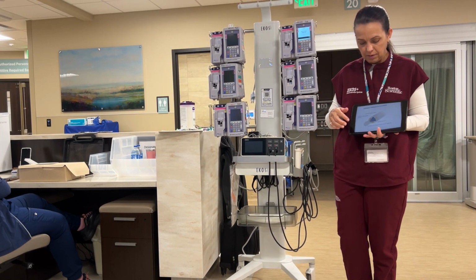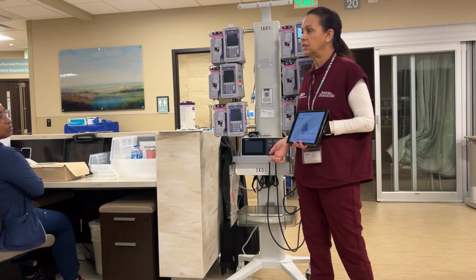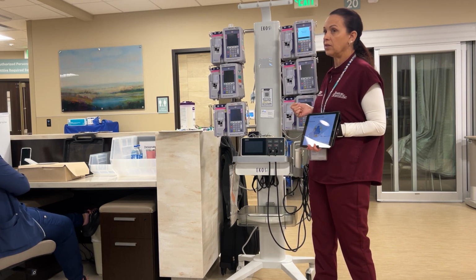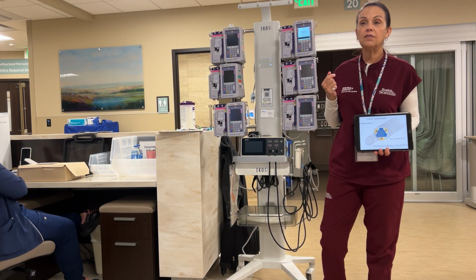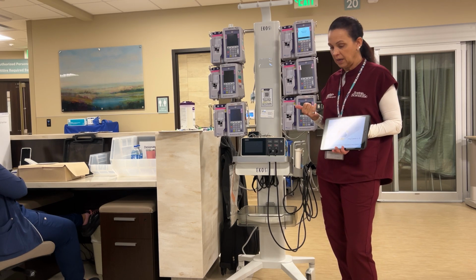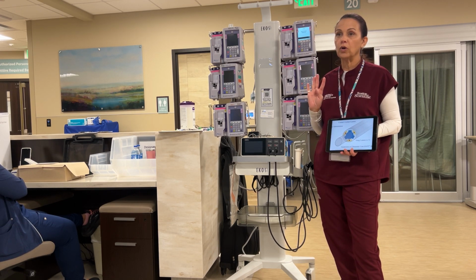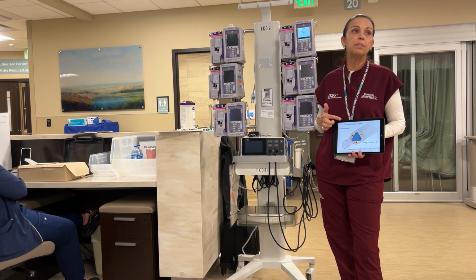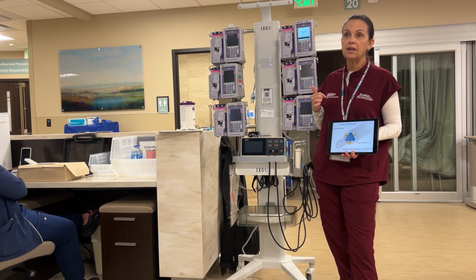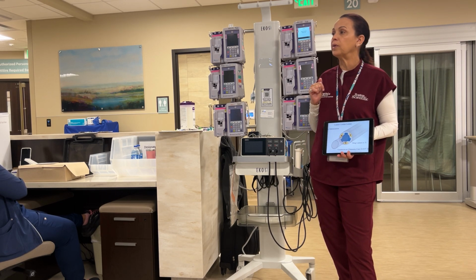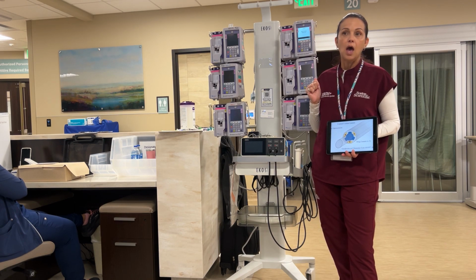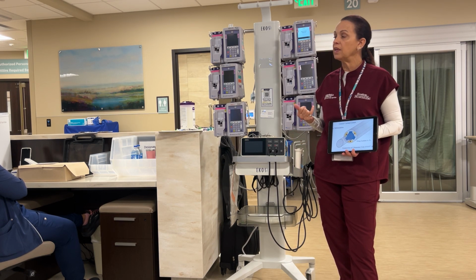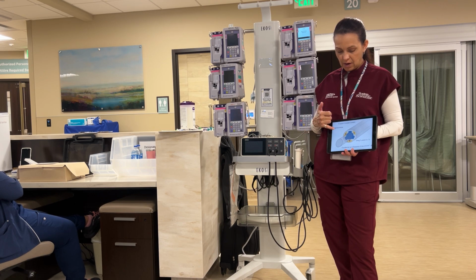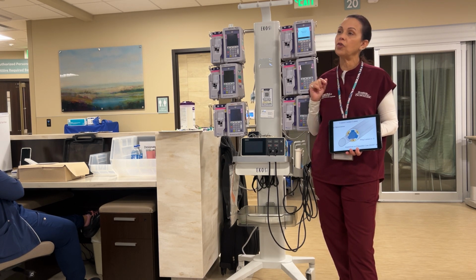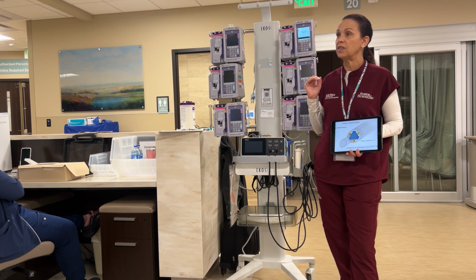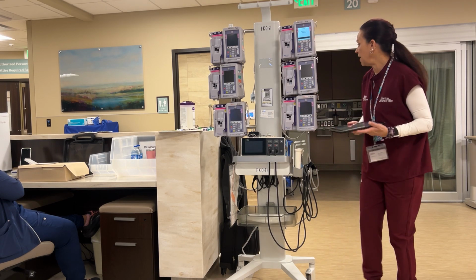So the catheter is a little different than a regular lytic catheter. Instead of a single lumen with an infusion segment, this catheter actually has 4 lumens. So we have 3 capillary-like drug lumens on the outside of the catheter, and then your coolant lumen, which is your central wire lumen. Now within that central wire lumen, the ultrasonic core is placed. Within the drug lumens, there are thermal sensors that regulate the power to the ultrasonic core. Now, I'm a hands-on kind of a girl.